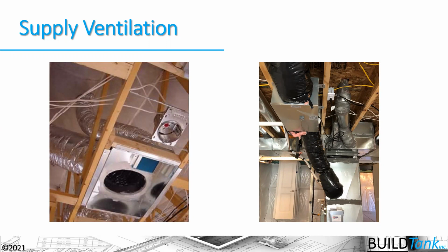So I'm bringing it in, maybe I am a slab on grade house and I don't have a basement where I can bring in air from the outside through the rim joist to the return side of the furnace. This picture on the left is bringing it to the return side of the furnace, but at a return grill. What's nice here is that I can filter that air. You can see that blue filter there as well. But again, it's basically more difficult to measure the flow of air coming through that duct in that type of system.